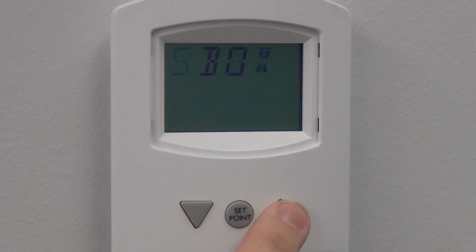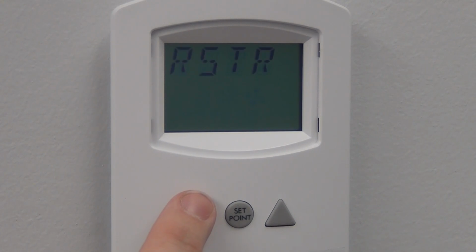The Box menu sets the K-factor, reheat, fan, and damper direction to close. The Flow menu sets the airflow limits. Under Advanced, I can change passwords and other special features of the controller. The Restore changes the displayed units and also restores the controller to factory settings. We are going to start in the Box menu.